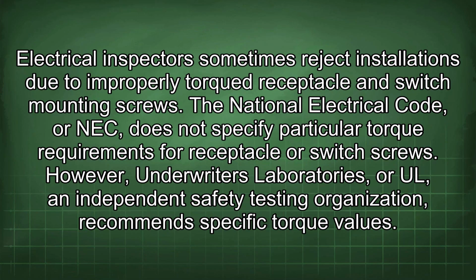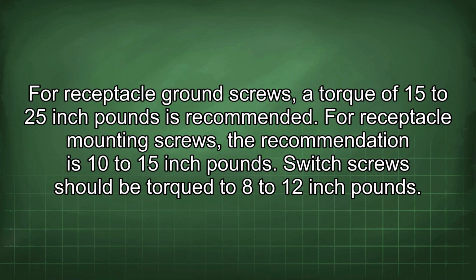Electrical inspectors sometimes reject installations due to improperly torqued receptacle and switch mounting screws. The National Electrical Code, or NEC, does not specify particular torque requirements for receptacle or switch screws. However, Underwriters Laboratories, or UL, an independent safety testing organization, recommends specific torque values. For receptacle ground screws, a torque of 15 to 25 inch-pounds is recommended.